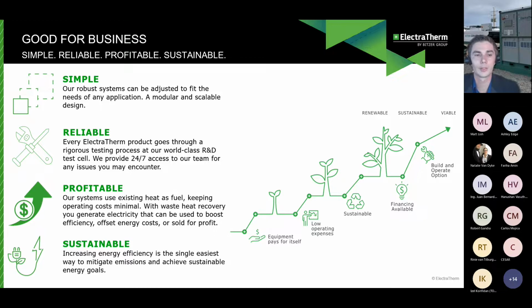The units are modular, scalable, and very easy to install. Again, very comparable to a radiator: a hot water supply and return, and then a motor rated circuit breaker for your electrical connection. Since we're using existing heat as fuel, operating costs are minimal. That's one of the biggest differences in our equipment in terms of total cost of ownership. There is no fuel cost to operate this besides what you already have. So again, we're using that to offset energy costs, but also to further utilize existing resources.